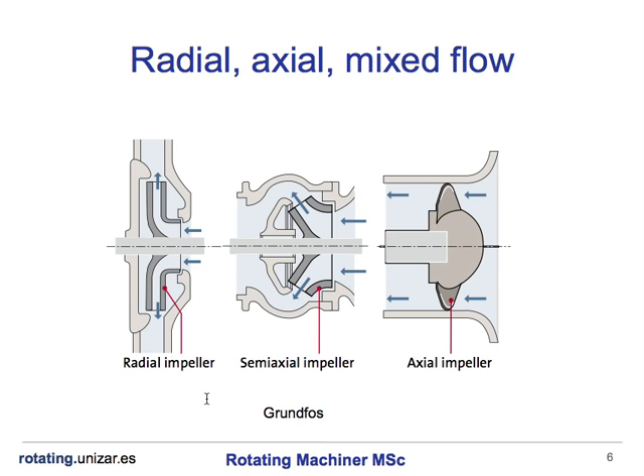If we look at the type of flow inside the impeller, we can classify impellers in three types: radial, axial, and mixed flow. In the radial impeller, you can see the actual direction of the flow compared to the radial direction. This impeller has a velocity with mostly or exclusively a radial component. In this other impeller, you can see the flow has mainly an axial direction.